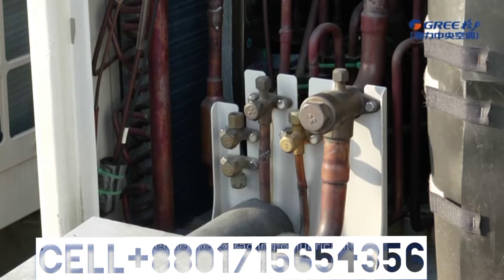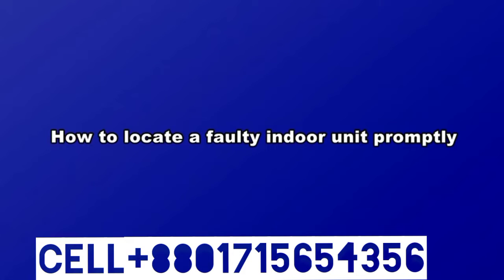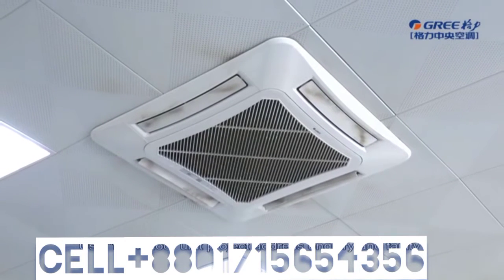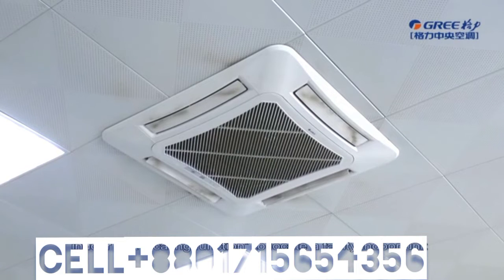Before the extracting of lubricant, the system must be stopped for at least 12 hours and the internal pressure of the system must be equal to or less than 0.2 megapascals. Otherwise, the overheat oil may burn the service personnel. How to locate a faulty indoor unit promptly. Use the Indoor Unit Project Address Inquiry and Faulty Indoor Unit Locating function to locate a faulty indoor unit or wired controller's corresponding indoor unit when multiple indoor units are running in one place. Detailed operation is as below.